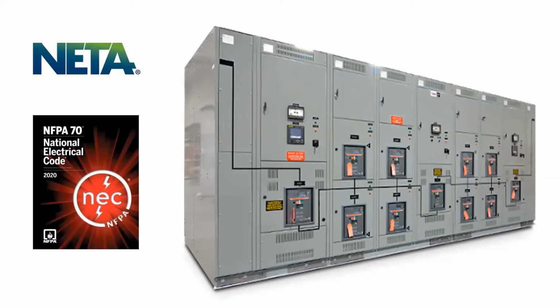There's quite a few of them. There's companies you can bring in, or you can take the breakers in to get bench tested if you need to. Sometimes that's an option, but usually not if it's already in the gear. If it's in the gear, you bring out a manufacturer rep, like Siemens will have someone come on site to test breakers and things like that.